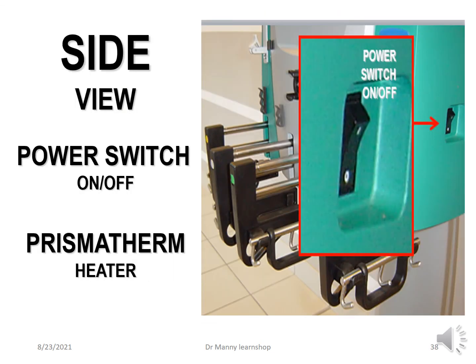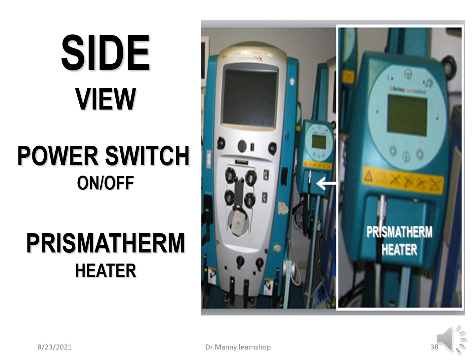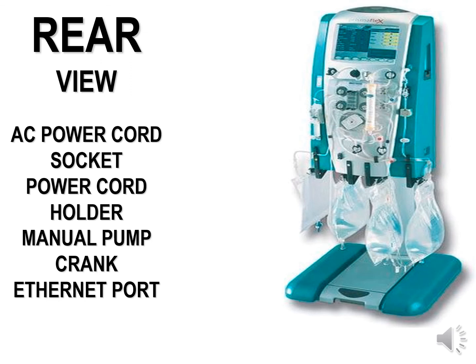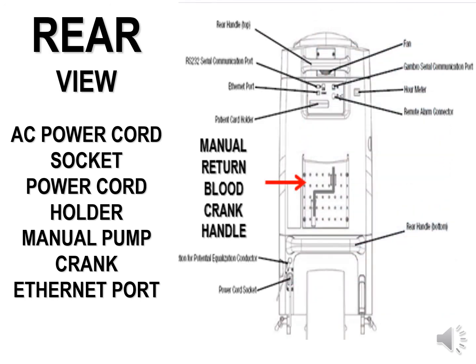On the side view, you've got the power switch, and you've got a connection for the Prismatherm heater. We'll be looking at these in a little bit more detail in a subsequent Learnshop. On the rear view, you've got the AC power cord socket, the power cord holder, the manual pump crank and the Ethernet port. And the manual pump crank is really important because again you may have to do a manual return of the blood if there's a power failure and the battery backup isn't effective. So you can always return the patient's blood either automatically, electronically with the machine, or with now the manual return blood handle crank.